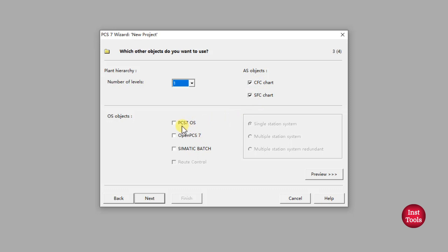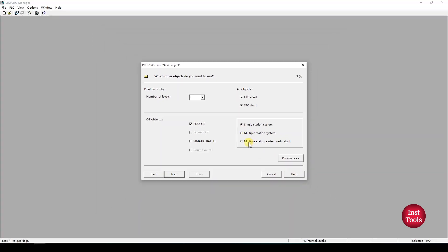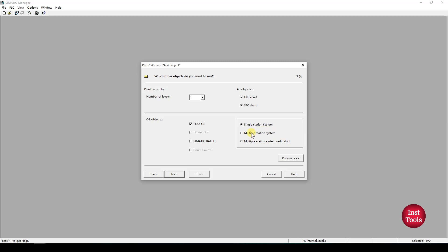We are choosing PCS7 OS single station. It will have a radio configuration for which mode you want to operate. Single station system means both ES and OS will be installed in a single system. Multiple station system means the configured system will be ES station and OS server will be separate, and you need to download it into a separate OS server. Multiple station system with redundancy means multiple OS redundancy servers. Click on Next.